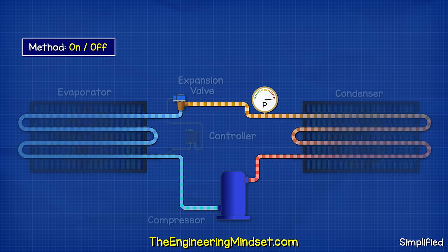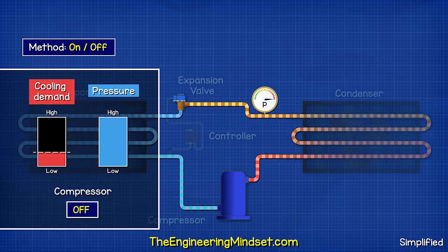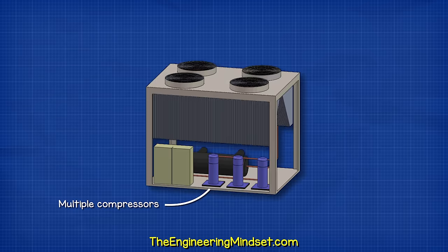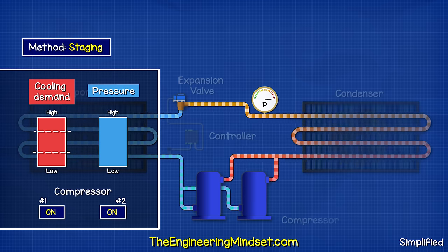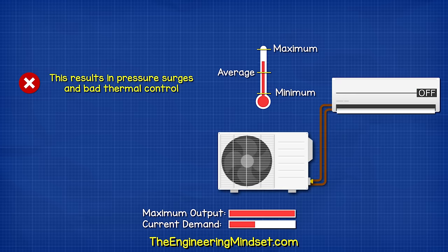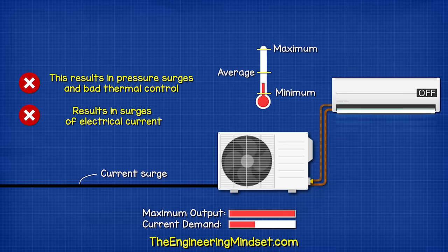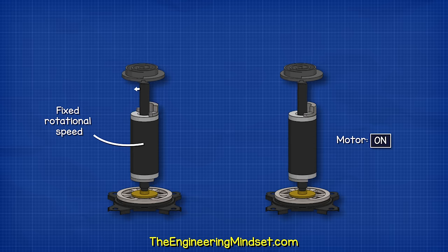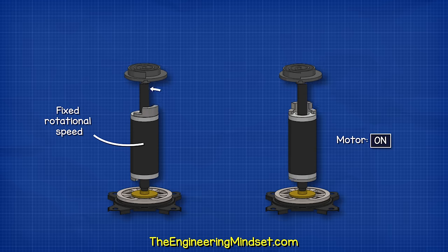Traditionally, scroll compressors would just be turned on and off to control the cooling capacity. The system is either completely on or completely off, there is no in-between. On larger systems with groups of compressors, they would simply be turned on and off at different stages to try and meet the cooling demand. This does give some modulation of capacity but it's not very good. Turning the system on and off causes pressure surges. It also causes bad thermal control and also causes electrical surges.